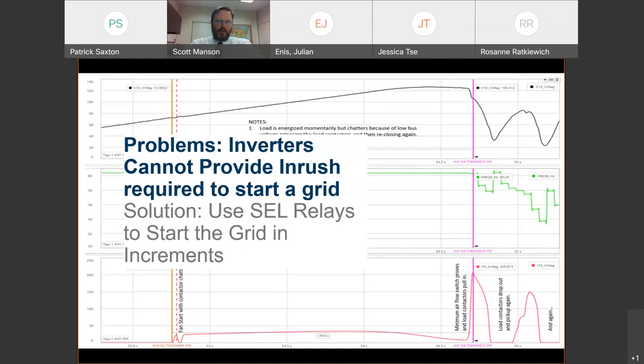Here's how it works. Number one, you isolate the inverter by opening circuit breakers and reclosers. It ramps up its voltage, thereby punching through the magnetic inrush of its local little transformer. Then the relays sequentially turn on loads in pieces, one at a time. You don't even need communication between the relays.